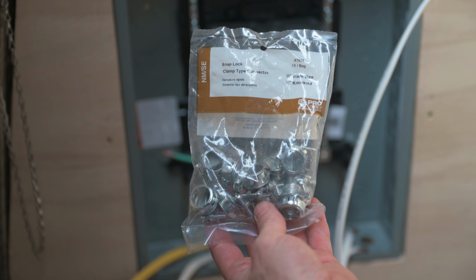In each of these holes, we want to install a strain relief clamp. These come in different sizes depending on your cable. They protect the cable from the sharp metal edges of the box, and when tightened, prevent any tugging on the cable from affecting the connections to the breakers. I bought some that are supposed to just snap in, but wow, those were hard to do.